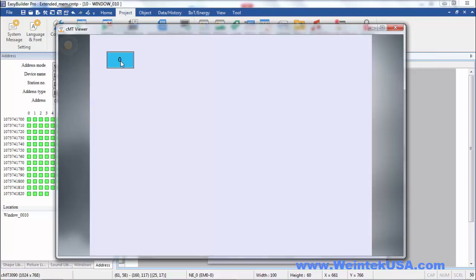Here's our numeric entry object. You can see that it's got a value of zero. I'm going to enter in a value of 100, and you see it holds it. Now, these are retentive registers that can be added. They can be formatted in any way except for binary.